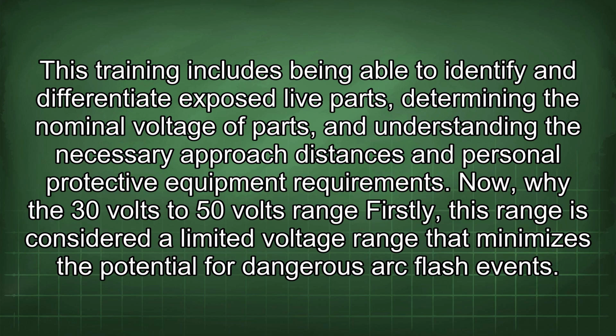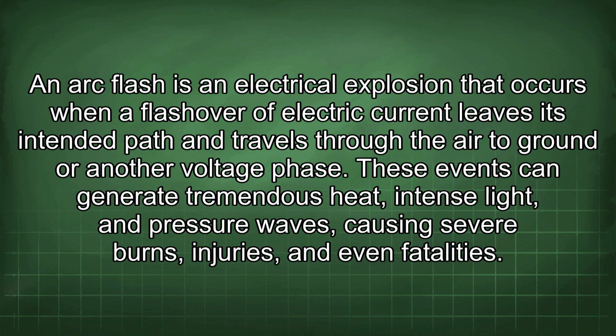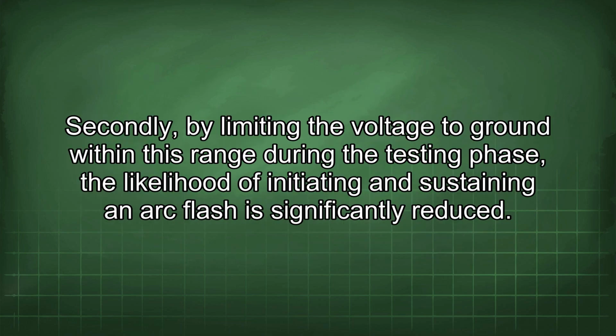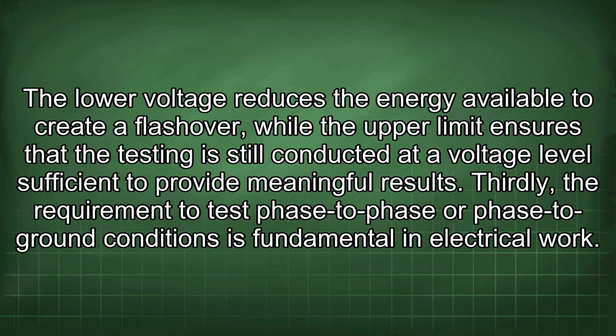Now, why the 30 volts to 50 volts range? Firstly, this range is considered a limited voltage range that minimizes the potential for dangerous arc flash events. An arc flash is an electrical explosion that occurs when a flashover of electric current leaves its intended path and travels through the air to ground or another voltage phase. These events can generate tremendous heat, intense light, and pressure waves, causing severe burns, injuries, and even fatalities. Secondly, by limiting the voltage to ground within this range during the testing phase, the likelihood of initiating and sustaining an arc flash is significantly reduced. The lower voltage reduces the energy available to create a flashover, while the upper limit ensures that the testing is still conducted at a voltage level sufficient to provide meaningful results.